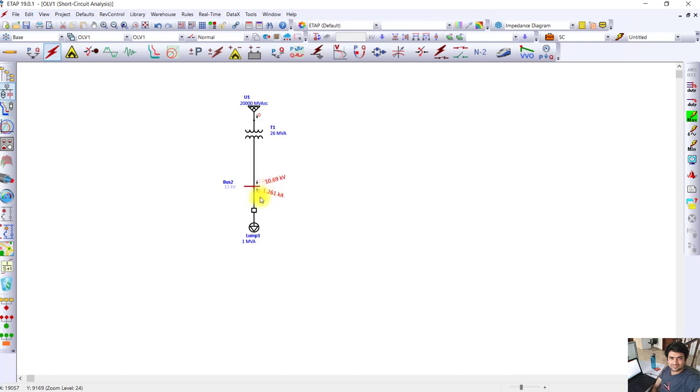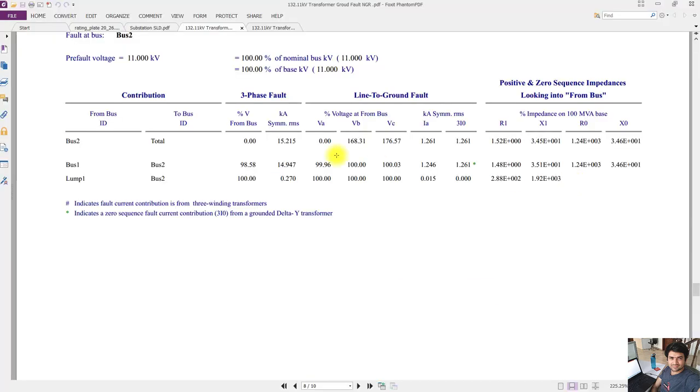Here are the results of this ETAP calculation. I will be adding this so you will be able to download this calculation results. Here you can see the system where NGR is connected - the line to ground fault current is 1.261 kilo amperes.